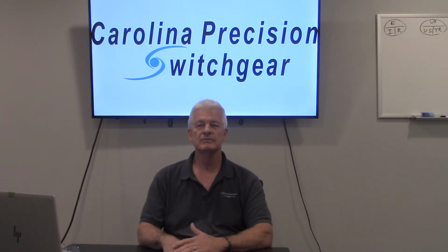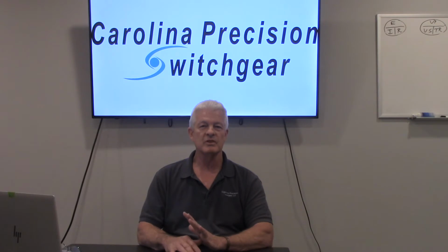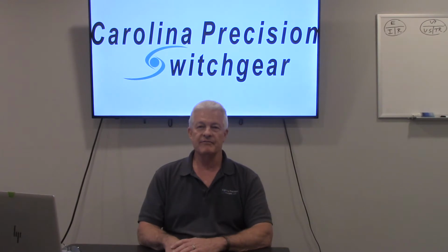So Doug, tell me why a circuit breaker would trip. There's several different reasons why a breaker may trip, but it's usually because of the overcurrent device that's on the circuit breaker. And you could have a phase to ground fault. You could have an inrush from like a motor that's going to make it trip, or you might just have someone in the control room that pushes a button that says trip the breaker, and the shunt trip and the breaker will open the breaker.